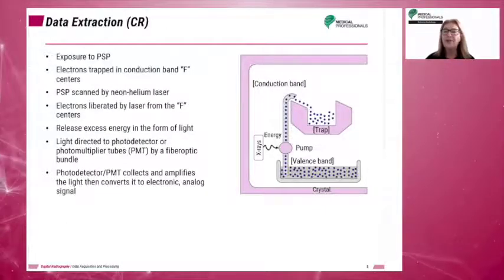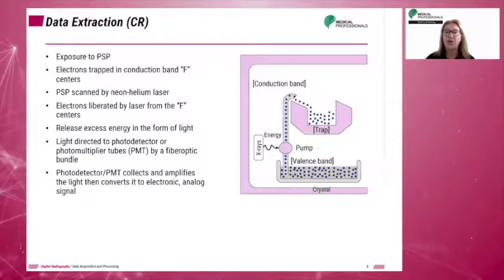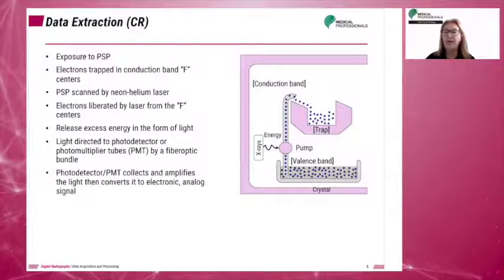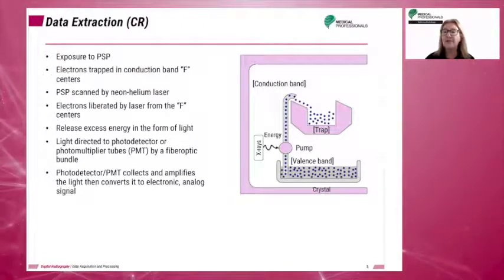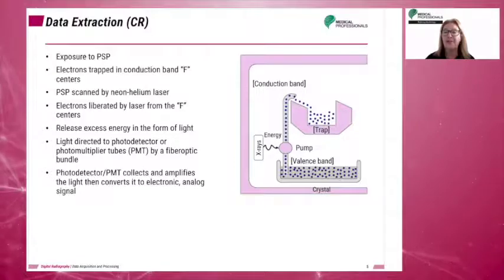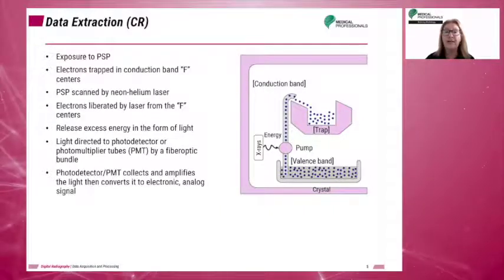All digital imaging employs a computer system to produce the visible image. With computed radiography, the imaging plate — or PSP — is exposed, causing ionization. The ionization then frees some of the phosphor atoms' electrons. These freed electrons become trapped in the conduction band of the imaging plate, creating electron holes, or F-centers.